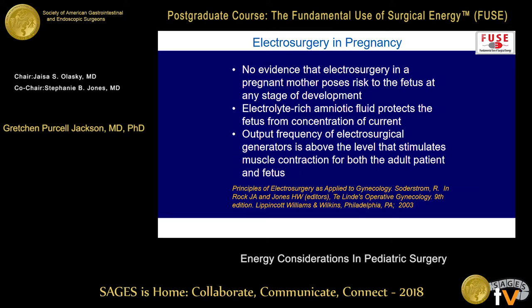Regarding our smallest patients — the unborn baby or fetus — there is no evidence that electrosurgical energy used in a pregnant mother poses any risk to a fetus at any stage of development. The electrolyte-rich amniotic fluid protects the fetus from current concentration, and the output frequency of electrosurgical generators is well above the level that stimulates muscle contraction in the mother or fetus. The only real risk is direct contact with the fetus, either during a C-section or possibly during fetal surgery.